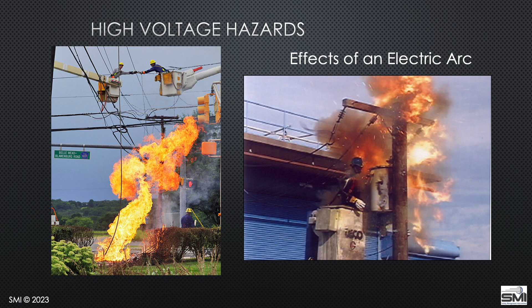Touching the electric line isn't the only hazard, there's also the electric arc. One thing I talk about involves meters. Guys pulling meters, often when a house is on fire, there are already short circuits inside. If the breaker hasn't tripped, they may get a flash pulling that meter out if there's a phase-to-phase fault. Just pulling a 120 volt meter out of a house can cause an electric arc that does damage, leading to house meter fires.